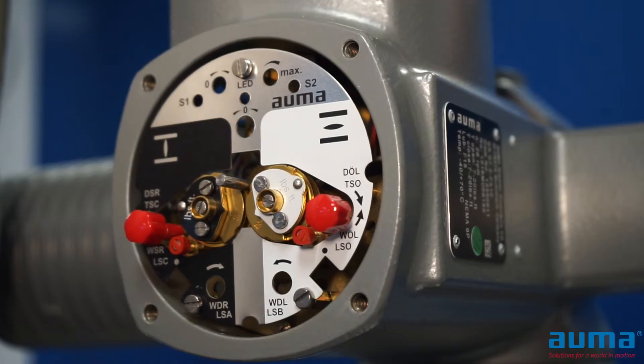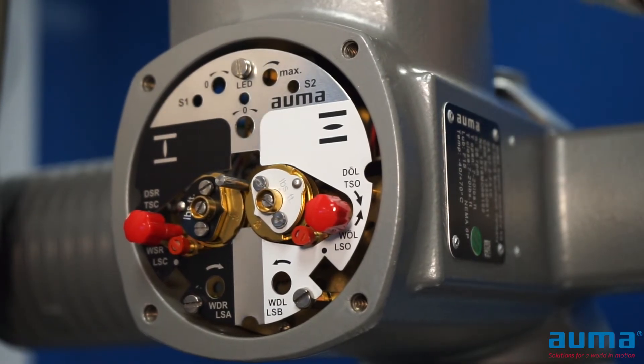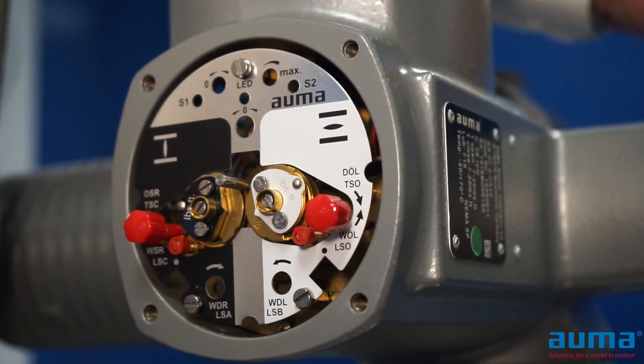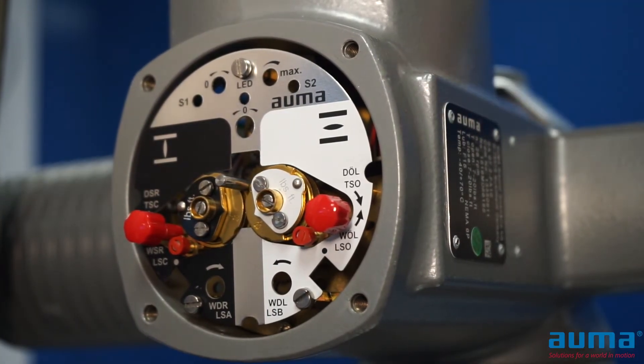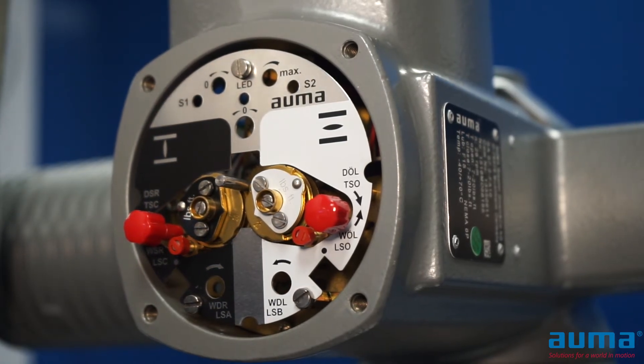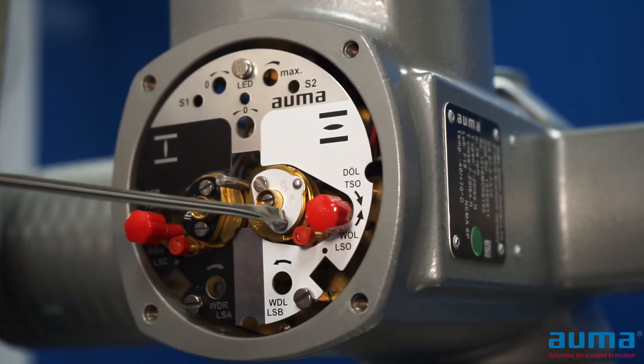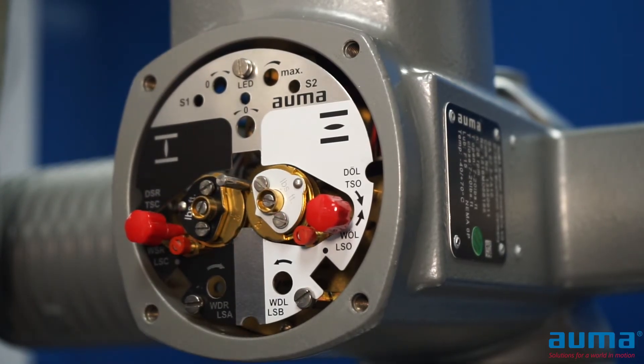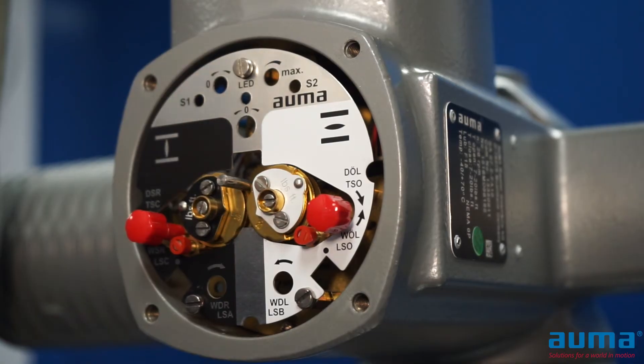When I turn my actuator hand wheel clockwise, my pointer will come off. And if I turn it back counterclockwise, my pointer will come on. Just like with the motor: if I run the motor closed, my pointer will come off; if I run my motor open, my pointer will come on to the trip mark. My limit switch settings are complete.